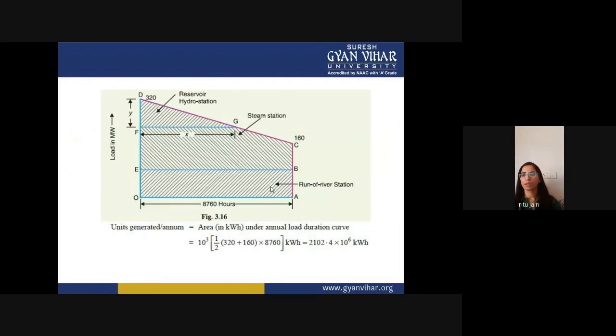So 320 megawatt is your maximum load and 160 is your minimum load. Units generated per annum is the area in kilowatt hour under the annual load duration curve. So you have to calculate this area, and you can easily get the units generated per annum, which is equal to 2102.4 into 10 to the power 6 kilowatt hour. So this is the unit generated per annum.